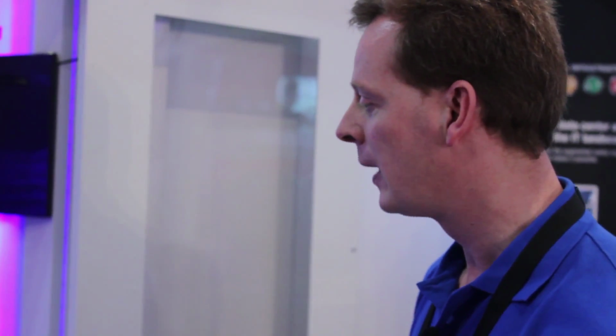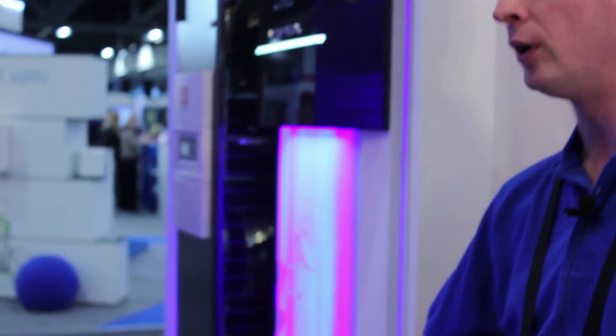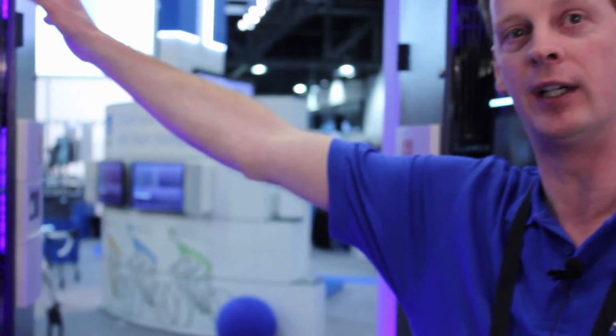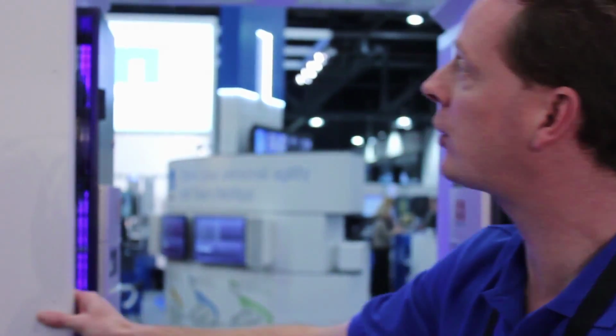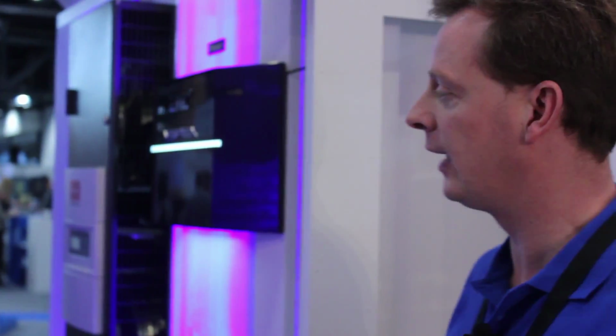does for you. So in terms of energy efficiency, what we can do is contain the cold air that comes up through the floor into the cold aisle, which gives you a much better way of actually having the air flow into the equipment. Okay, so we have the doors here which seal at the front of the cold aisle, and you have the same thing at the rear.